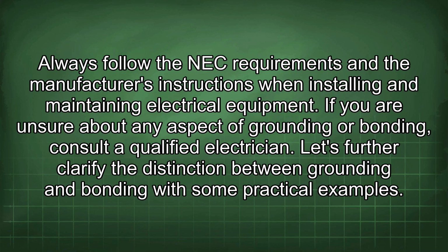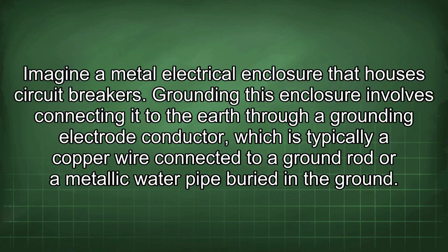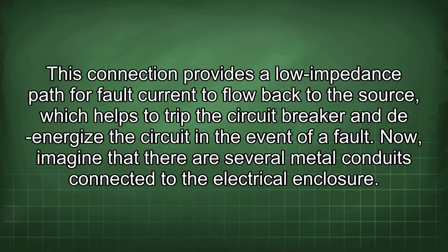Let's further clarify the distinction between grounding and bonding with some practical examples. Imagine a metal electrical enclosure that houses circuit breakers. Grounding this enclosure involves connecting it to the earth through a grounding electrode conductor, which is typically a copper wire connected to a ground rod or a metallic water pipe buried in the ground. This connection provides a lower impedance path for fault current to flow back to the source, which helps to trip the circuit breaker and de-energize the circuit in the event of a fault.